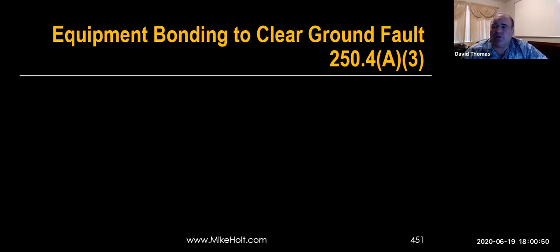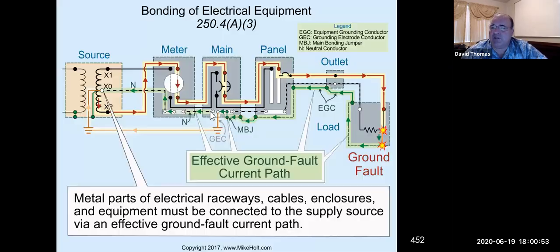And we will use equipment bonding to clear any ground faults. And what we're saying is we have to create effective ground fault pathways, and that's the electrician's job, to create anything in green in here. Those are effective ground fault pathways. If we ground the metal container and we take a wire and ground every outlet, we created a pathway all the way back to the source, to the transformer. Okay, so there's an effective pathway all the way back to the transformer. And the main purpose, again, is to facilitate the operation of the breaker. So the breaker will trip on ground faults. We want it to trip on ground faults.